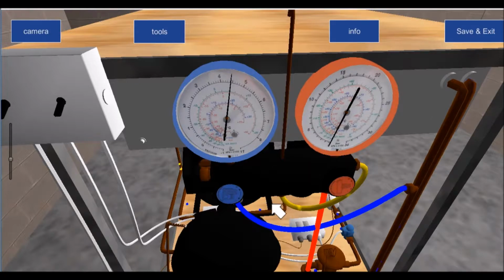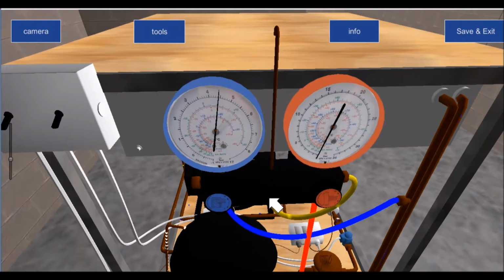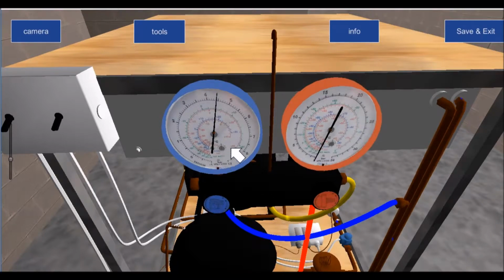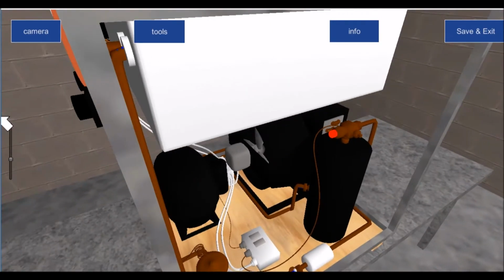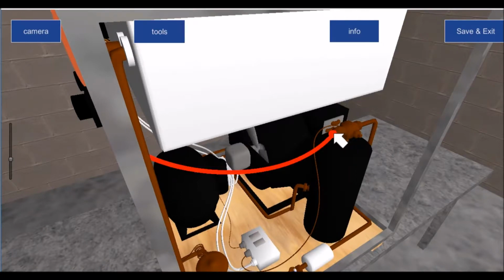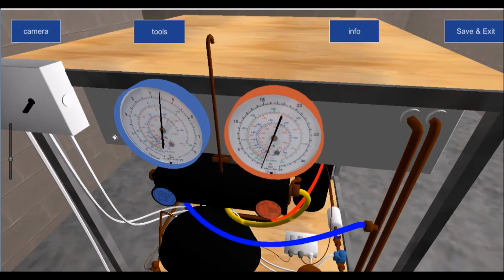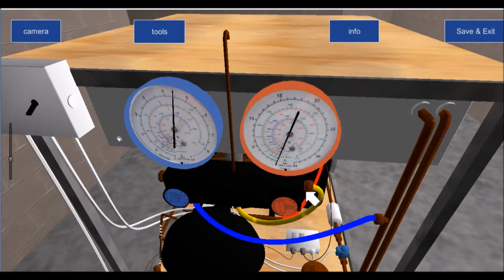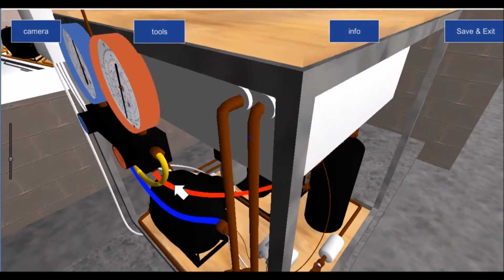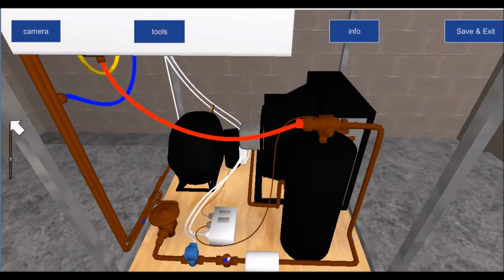And the reason for that is that if I want refrigerant to go from my low side, which we have here at the moment, and remember when we go through the purging process, one of the other things that we do is we fit the red line here, okay, and you'll notice that the red gauge is still registering 0. That's because we're using a different valve here. The service valve that we're using here is a service valve that requires a valve ratchet to crack it.